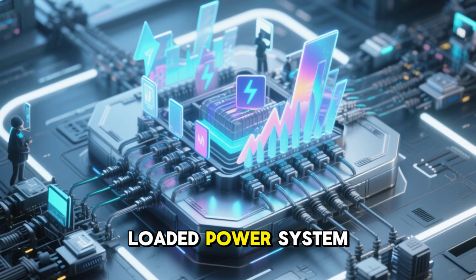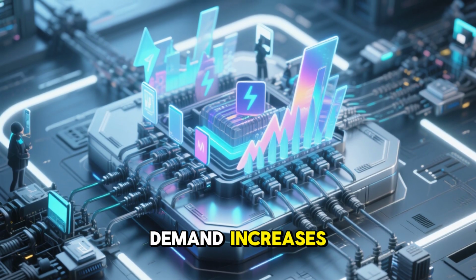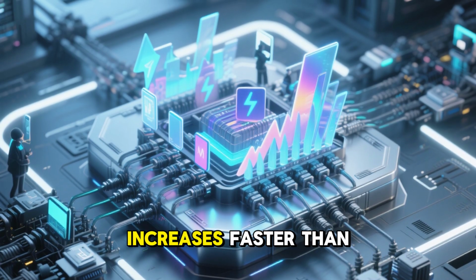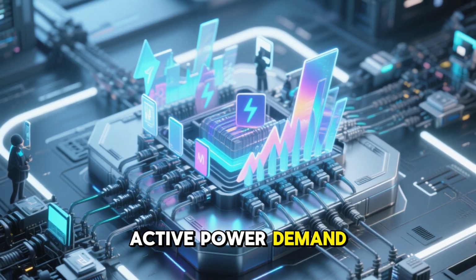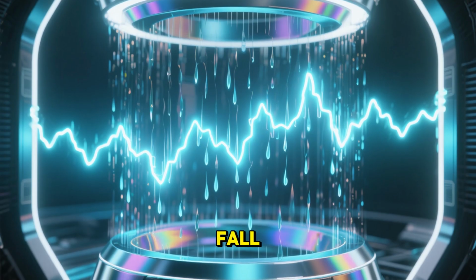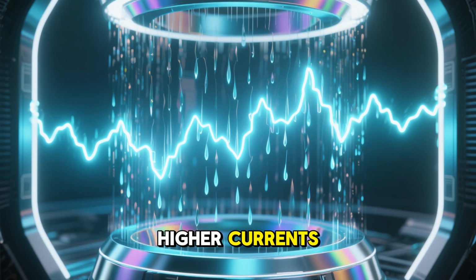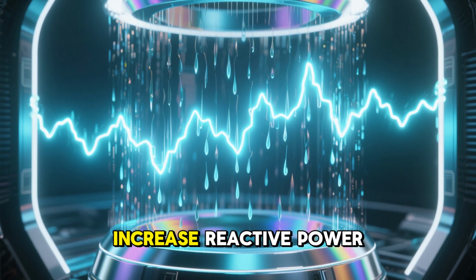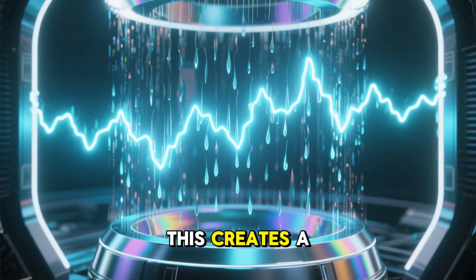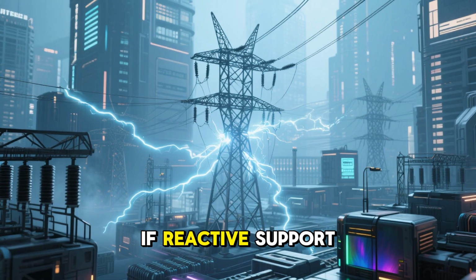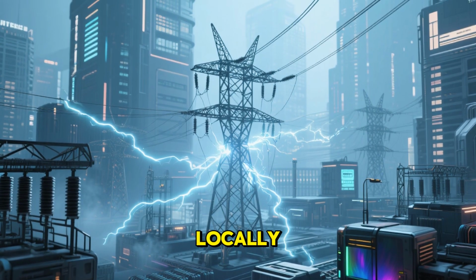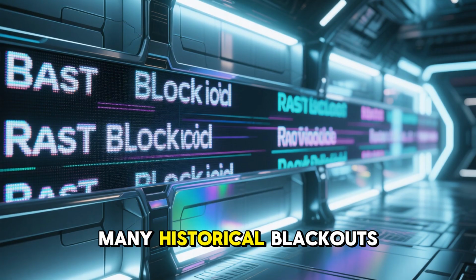Imagine a heavily loaded power system. Demand increases. Reactive power demand increases faster than active power demand. Voltage starts to fall. Lower voltage causes higher currents. Higher currents increase reactive power consumption. This creates a dangerous feedback loop. If reactive support is not available locally, the system collapses. Many historical blackouts followed exactly this pattern.